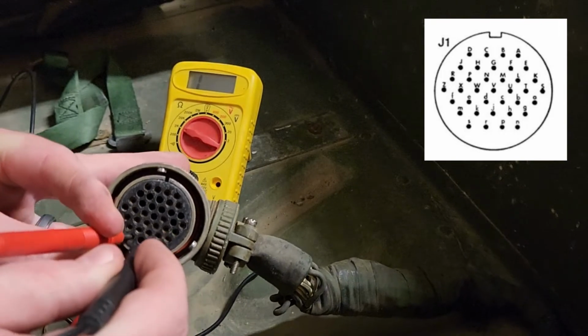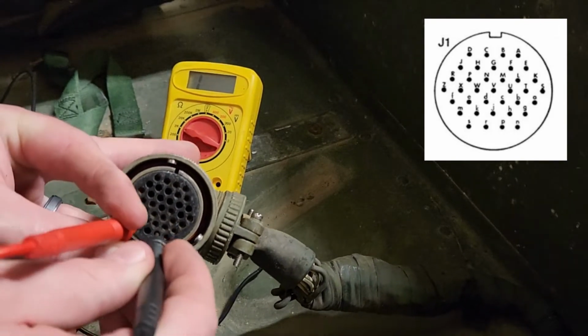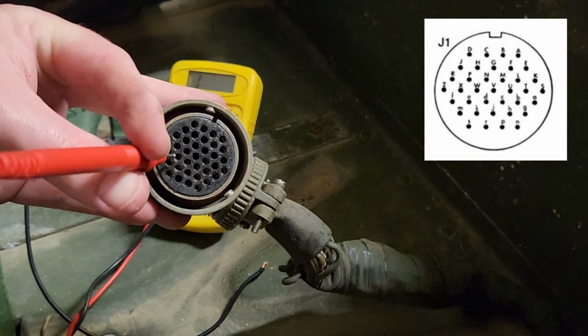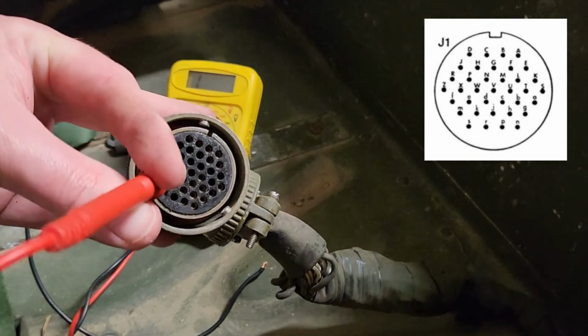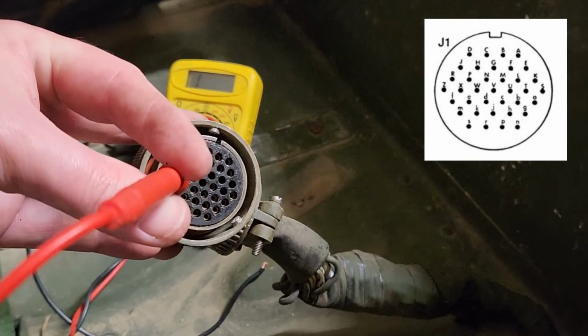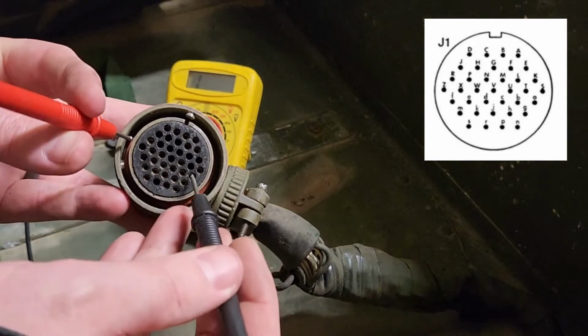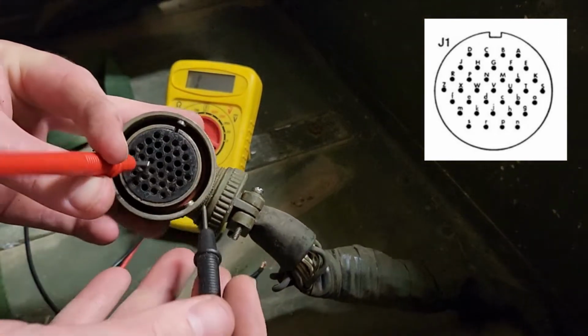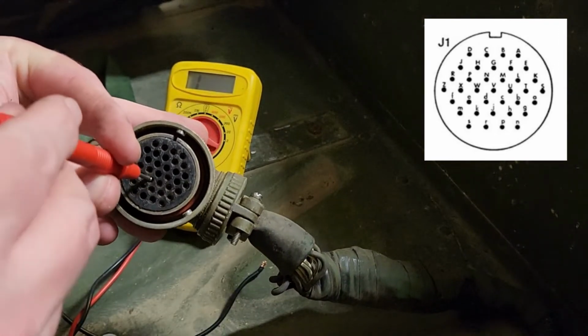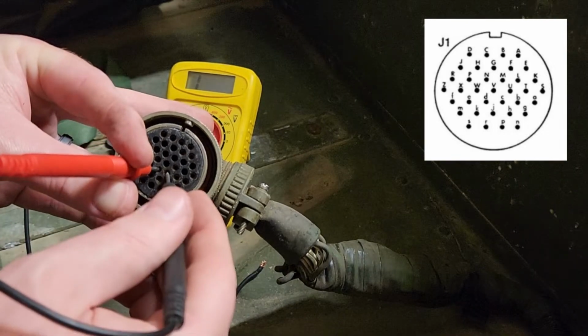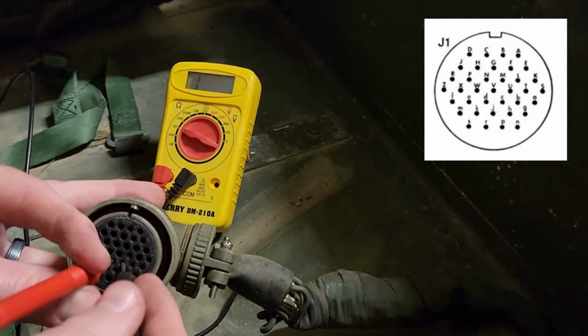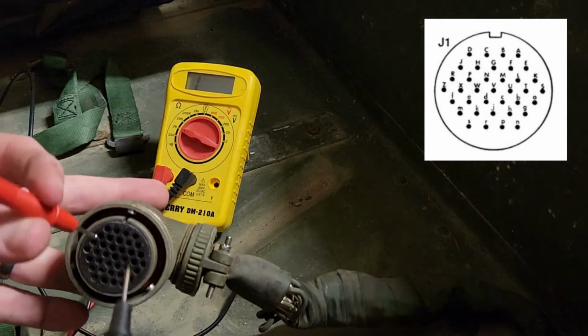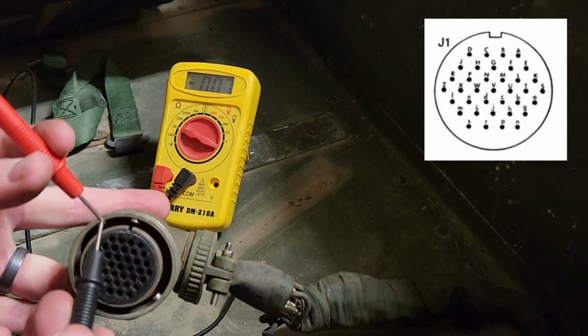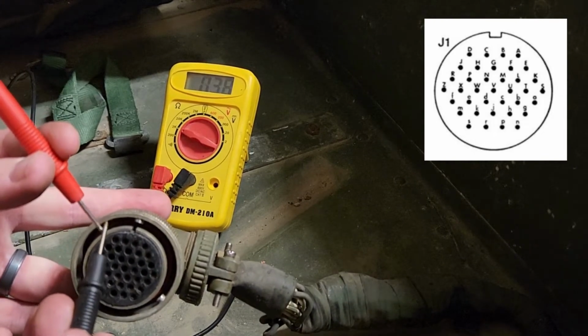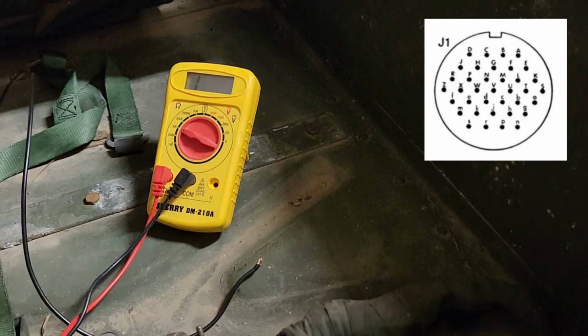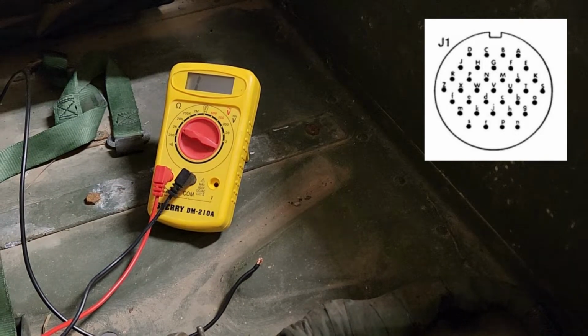I should be getting resistance across that, and I'm not measuring any. So the next one they want us to test is D, which is right here - A, B, C, and D. I'm going to test there, and you can go to either C or P as well. If you look at the voltmeter, I'm getting no resistance, but I know it's working because I can get a resistance measurement off of my connections just touching. So I think I've got a bad TPS for sure.